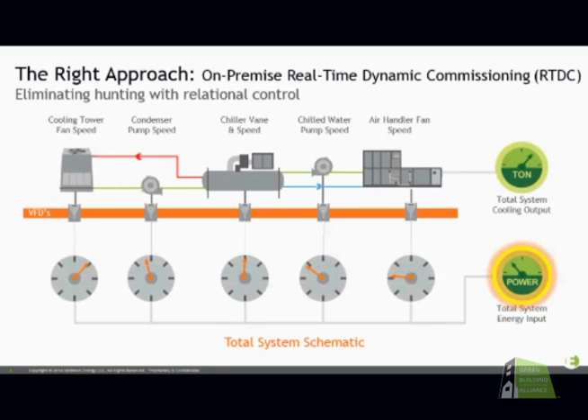And even if you're able to reduce it a little bit, a 10% reduction, if you take 0.9, 90% speed, 90% flow, cube that, you're saving 27%. So now you're using about 73 horsepower just by that small reduction. So that's why it's very important, and we're big advocates of all variable speed plants.